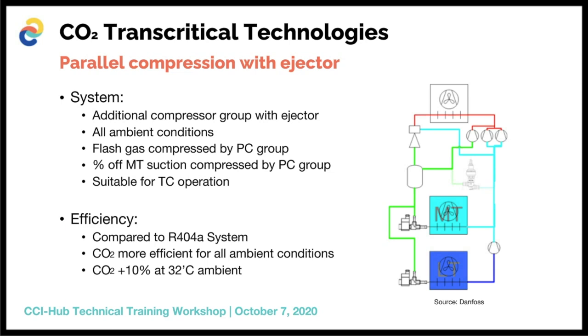With the introduction of this technology, CO2 has been made energy efficient compared to any type of system and up to any ambient conditions. So this is definitely a suitable solution for extreme high ambient conditions, with no additional allowances made for energy efficiency. At the ambient point of 32 degrees Celsius, 10% and more energy saving can be found compared to an R404A system.